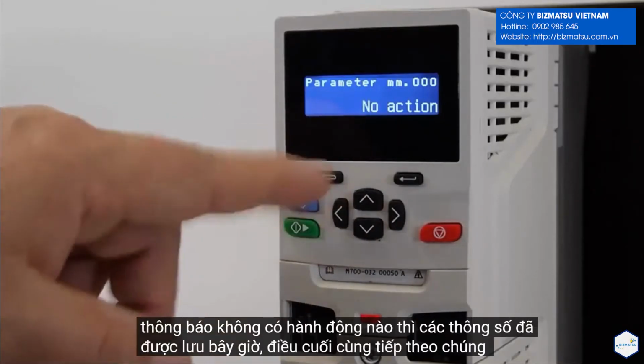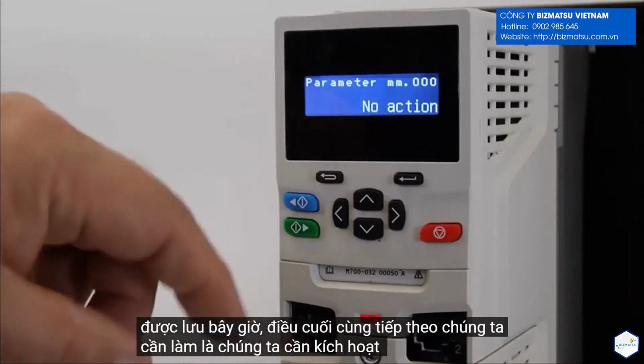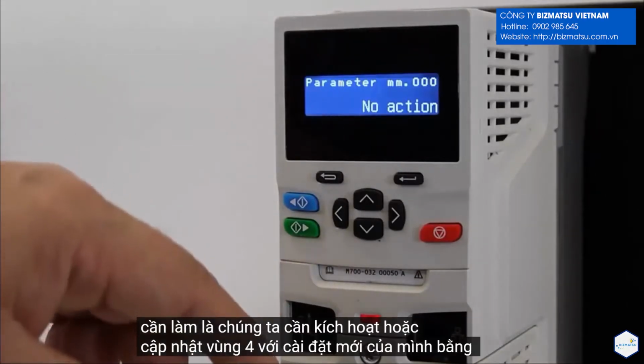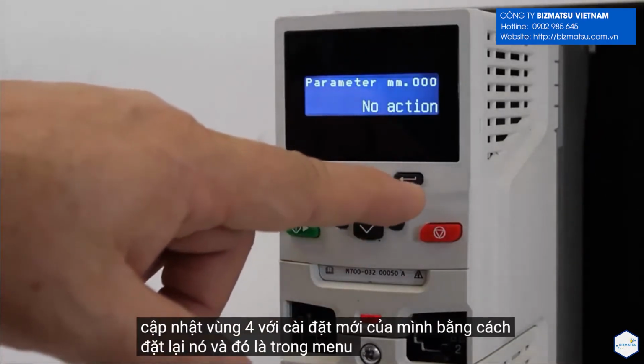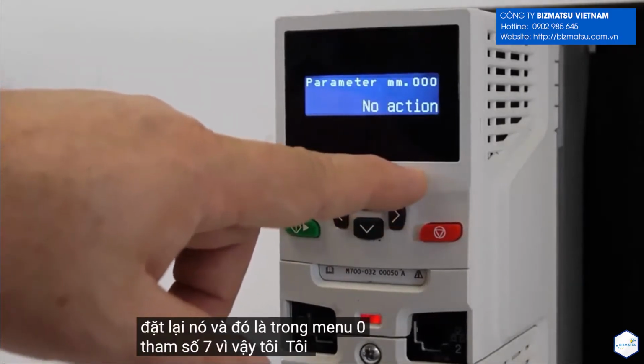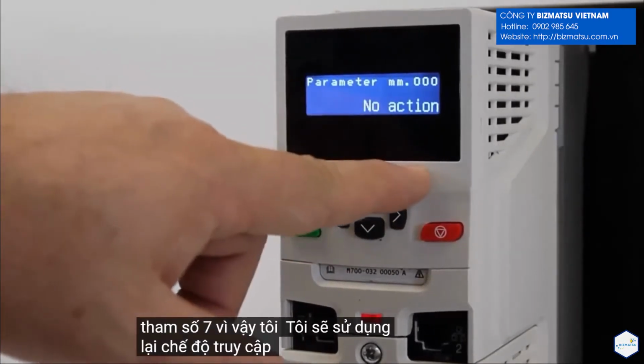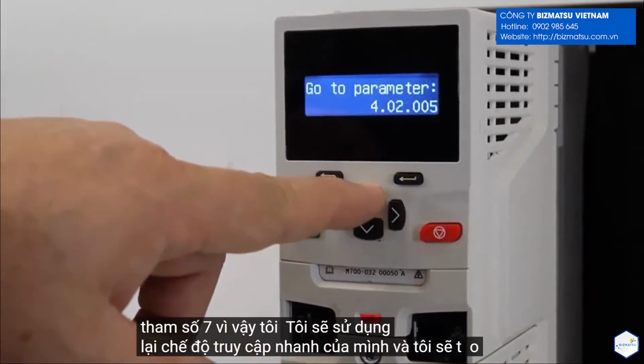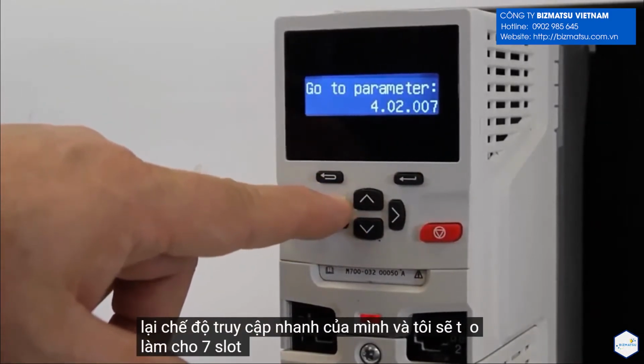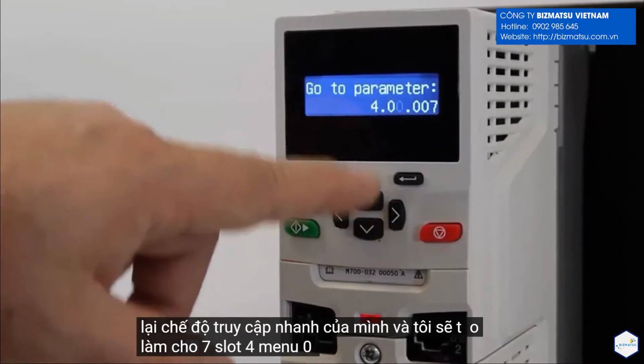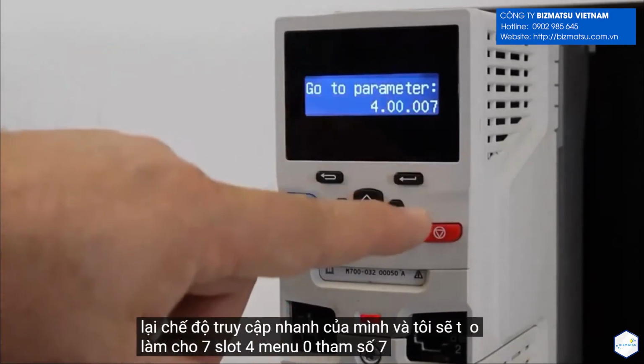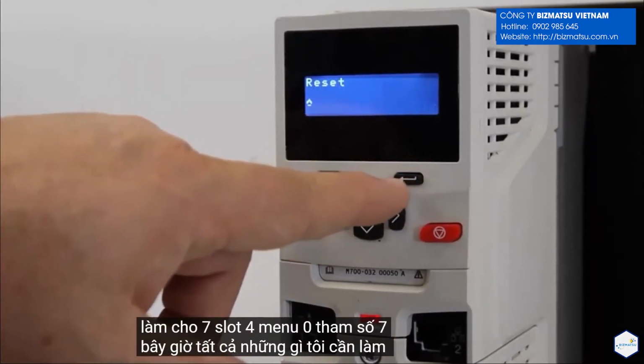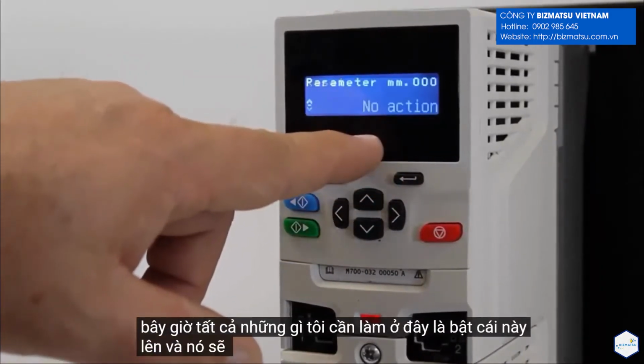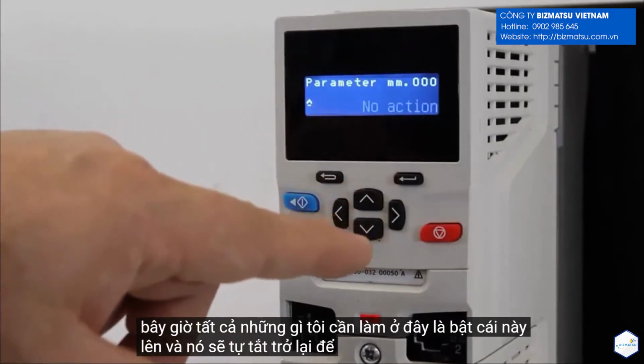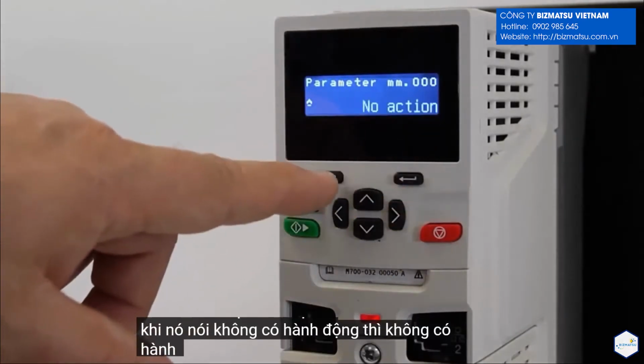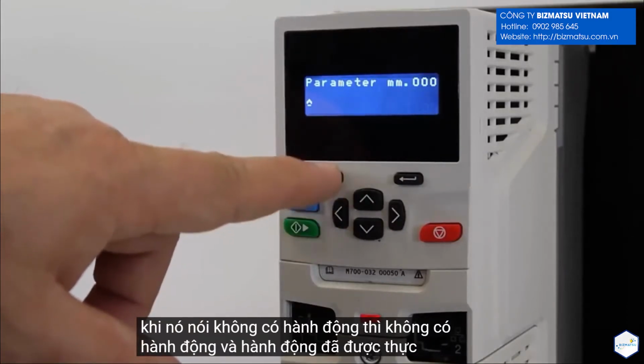Now, the last thing we need to do is activate or update slot 4 with our new settings by resetting it. And that's in menu 0, parameter 7. So I'm going to use my quick access mode again, and I'm just going to make that a 7. Slot 4, menu 0, parameter 7. Now all I need to do here is turn this on, and it'll turn itself back off. So when it says no action, there is no action, and the action has been performed.